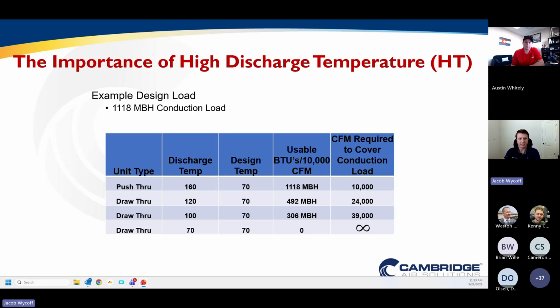And only once you raise that discharge temperature up above your space temperature do you get BTUs that are usable to cover the conduction load of the space. We call this usable or net BTUs. So take, for example, a blow-through style unit that we allow to discharge at 160 degrees. In this example, you're going to get 1,118 usable BTUs for every 10,000 CFM of air that you provide to the space. So to cover the conduction load in this example would require 10,000 CFM.